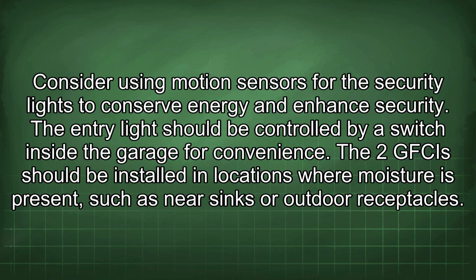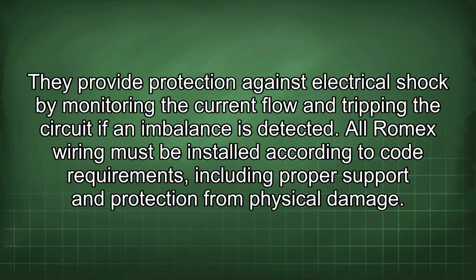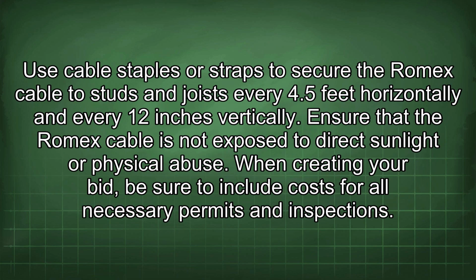The two GFCIs should be installed in locations where moisture is present, such as near sinks or outdoor receptacles. They provide protection against electrical shock by monitoring the current flow and tripping the circuit if an imbalance is detected. All Romex wiring must be installed according to code requirements, including proper support and protection from physical damage. Use cable staples or straps to secure the Romex cable to studs and joists every 4.5 feet horizontally and every 12 inches vertically. Ensure that the Romex cable is not exposed to direct sunlight or physical abuse.